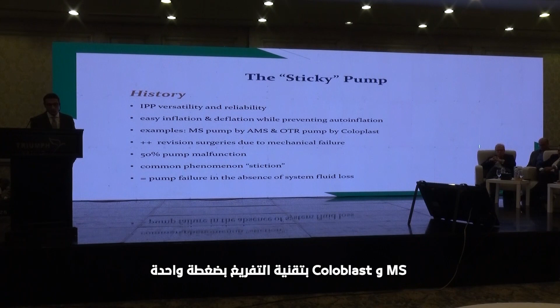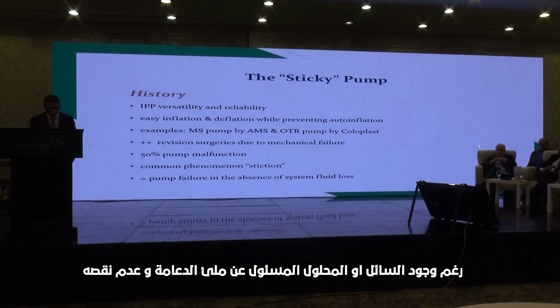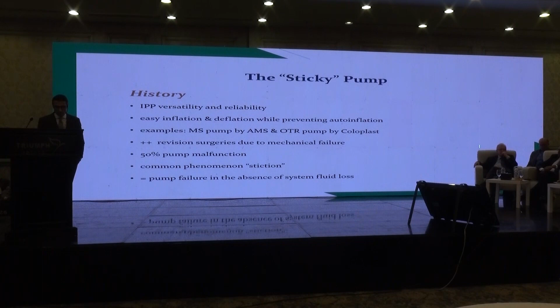Reviewing the literature, the most common causes of revision surgeries are due to mechanical failure. Interestingly, almost 50% of these revision surgeries or mechanical failures were due to pump malfunction, with a common phenomenon called stiction, meaning pump failure in the absence of system fluid loss.